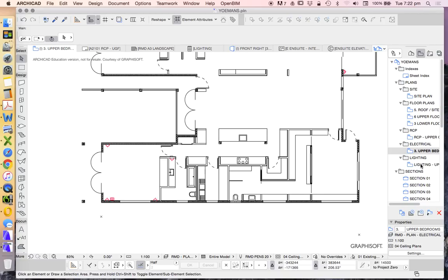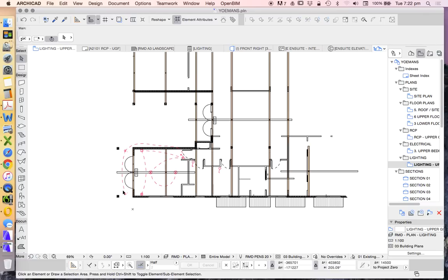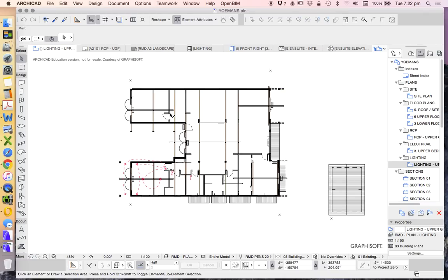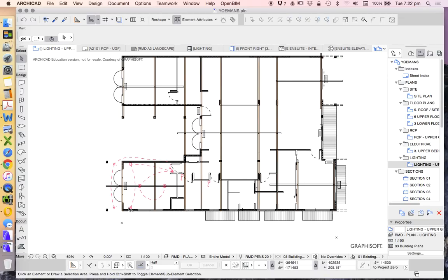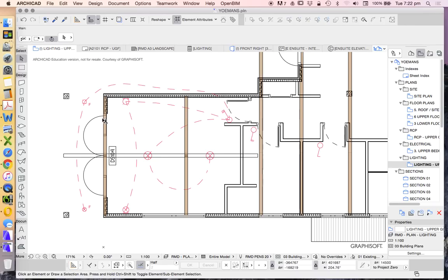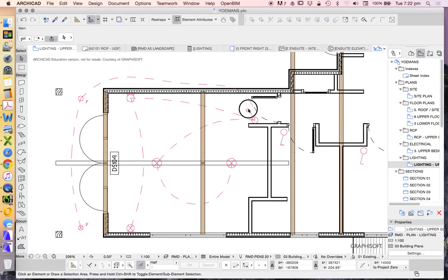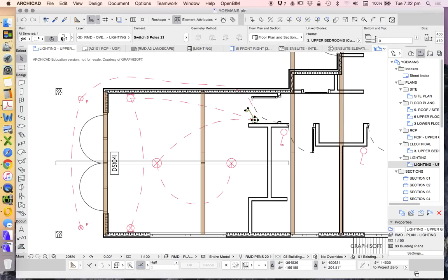The other type that I use is called a lighting plan, and I do that separately. So you see that my electrical plan was based on a floor plan, and my lighting plan is based on a reflected ceiling plan. So just, again, whole house, I'm just focusing on a little bit at the moment. What is a lighting plan? What we're doing is showing switching. So again, let's go into this.